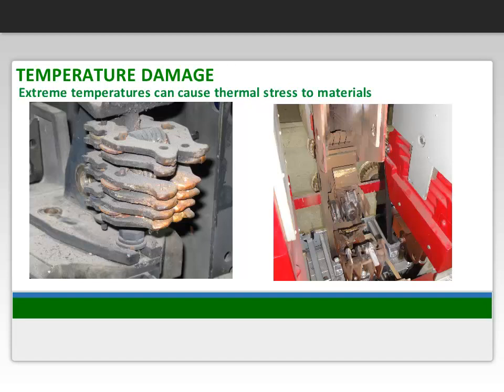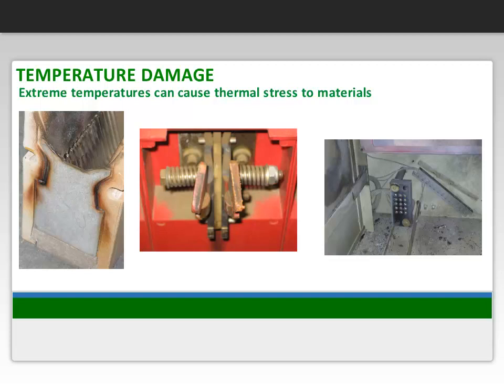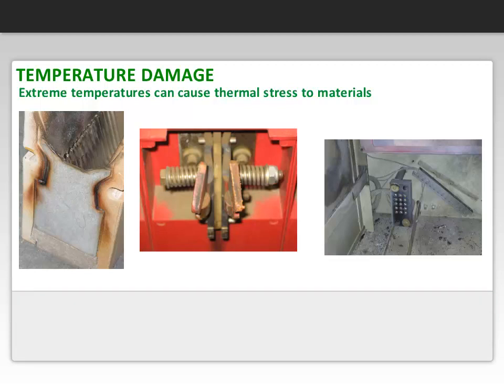Look for signs of burnt residue and signs of extreme temperature that is not natural. These items were exposed to the most extreme heat conditions, such as an arc flash. In many cases, these signs are the result of a breaker clearing a fault. Typically, arc chutes show this excess temperature. Another area to examine is all insulation for traces of burn. All of the affected items shown required replacement. Arc chutes, contacts, contact springs, and disconnects can all experience extreme temperatures during normal interrupting operations. These components should be carefully inspected for signs of overheating and deteriorated insulation. These components should never be reused when performing a basis of inspect and test.